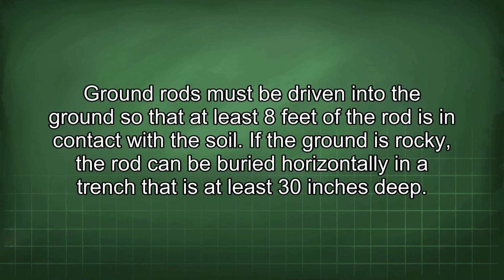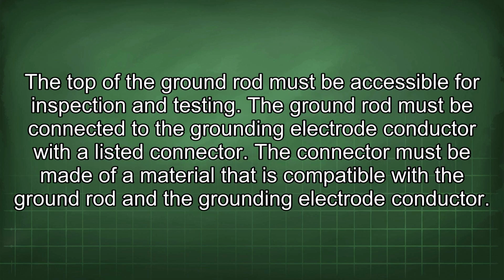If the ground is rocky, the rod can be buried horizontally in a trench that is at least 30 inches deep. The top of the ground rod must be accessible for inspection and testing. The ground rod must be connected to the grounding electrode conductor with a listed connector. The connector must be made of a material that is compatible with the ground rod and the grounding electrode conductor.